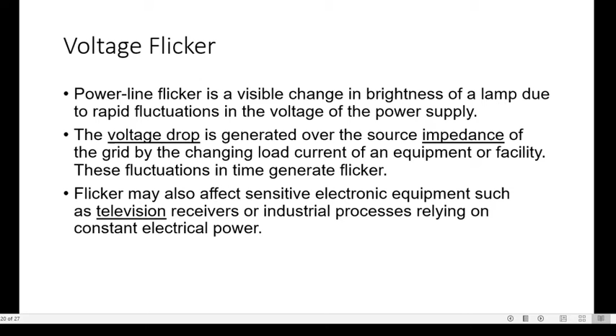Flicker may be produced, for example, if a steel mill uses large electric motors or arc furnaces on a distribution network, or by the frequent starting of an elevator motor in an office building, or if a rural residence has a large water pump starting regularly on a long feeder system. The likelihood of flicker increases as the size of the changing load becomes larger with respect to the prospective short circuit current available at the point of common connection, and the intermittent load as we discussed.